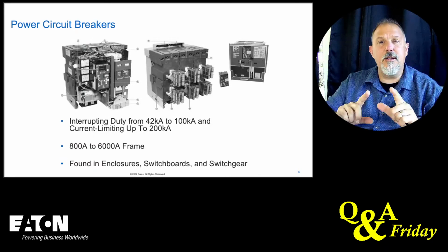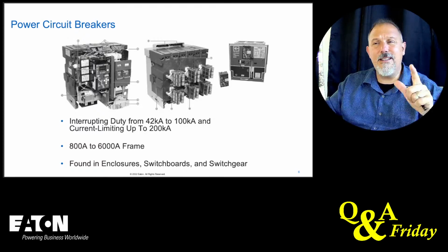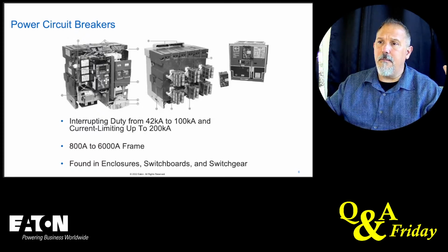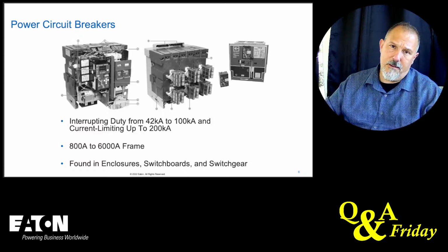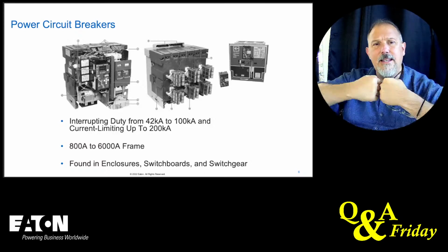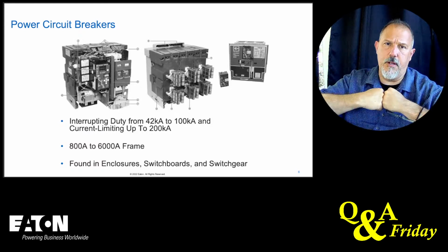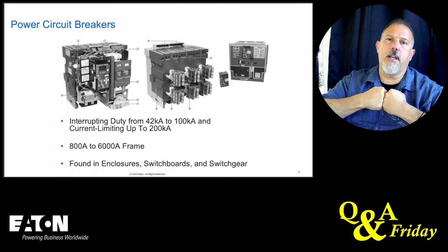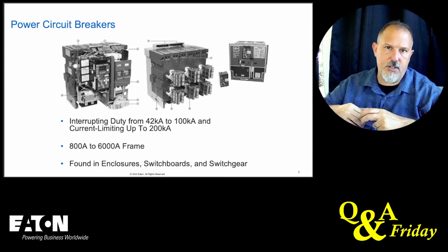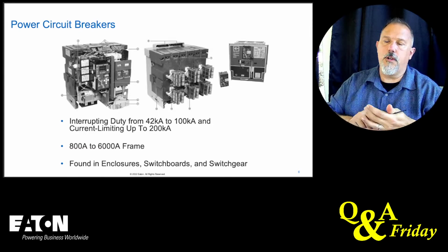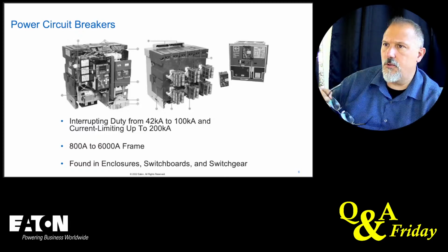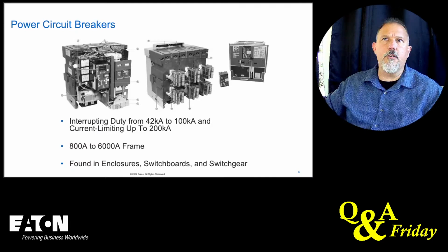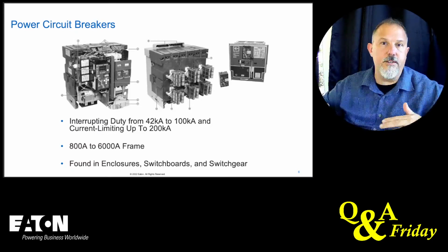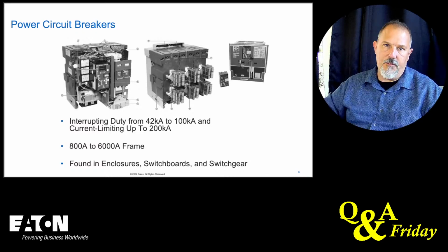Now, again, current limiting by definition. Do they limit current? Yeah, sure, they sure do. Can they open fast? They sure can. That's not why you bought an 800 amp insulated case circuit breaker, right? You're there because you want all those guys downstream, all those puppies downstream to do the job. You're there to hold those contacts closed so you don't have cascading events, you don't cause larger outages, you don't want to stop because of all these inrush motors and whatnot, and transformers that are all energizing in your power distribution system all at once. You don't want to trip on any of that.